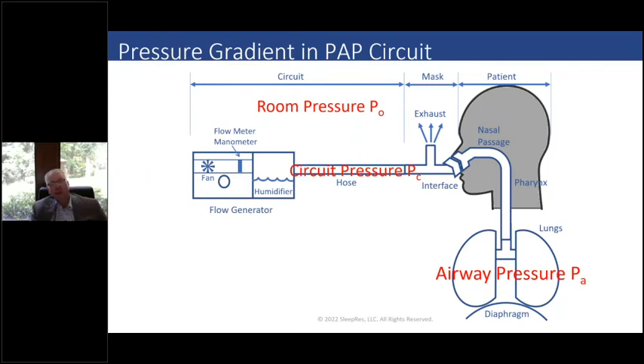You have the weight of 34 feet of water on you with normal barometric pressure. So, pressure gradient in the system of the PAP circuit. You're going to see this a lot today. You see the fan over here to the left, the turbines, which generate the pressure, which create flow. And then you're going to see that they have a flow meter, which adds resistance. We're going to go through this a lot more later. But I want you to understand that there's a pressure gradient: the room pressure is zero, and then there's a pressure in the circuit.